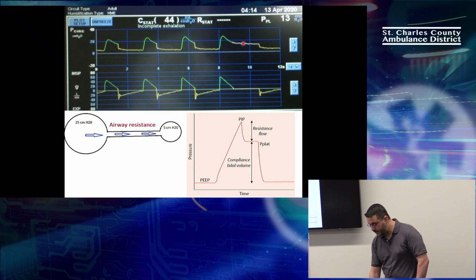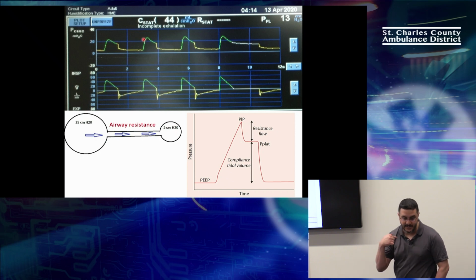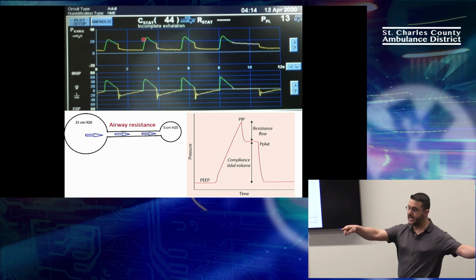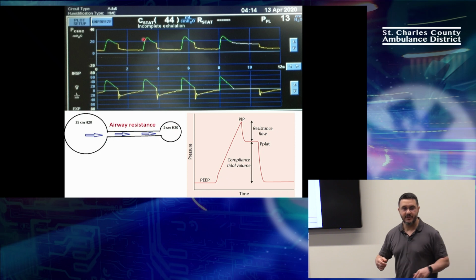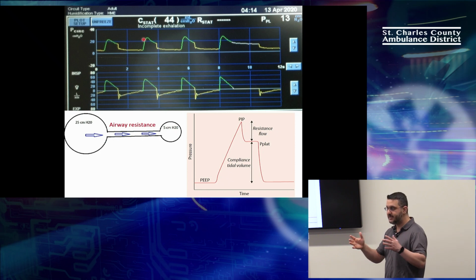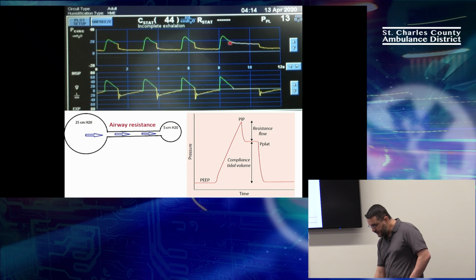So this is a breath hold right here. You pause the breath. That means the valve shut down, and they can actually measure the plateau pressure right there. So do you see the difference between the peak pressure? This is pressure up here, and this is time. And you have that graph on your ventilators. The x-axis is time. The y-axis right here is pressure. So peak pressure is the pressure that the ventilator has to overcome, the tubing, all that fancy equipment in the stack. Maybe you stepped on some of the tubes. Maybe they have asthma. All these pressures that are resistance, that is the peak airway pressure, this guy. And this is the plateau right there. Do you guys see it? They call it plateau because it looks like a plateau. Nothing fancy about it.